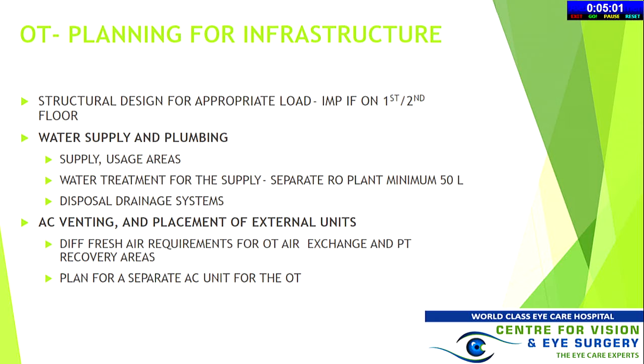So the AC venting and placement of external units needs to be planned, because your pipes are going to run across the roof, so do that initially before you put up the vertical structures. There are of course different fresh air requirements for OT air exchange and patient recovery areas. Remember that you need an air exchange of between 20 to 25 inside the operation theater, and Kumran will touch upon more in detail. Always preferably plan for a separate AC unit for the operation theater so that the cooling can be more robust.